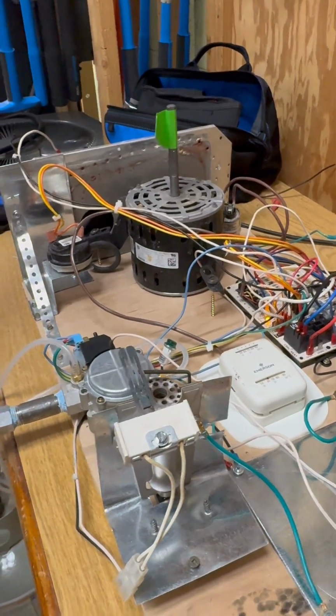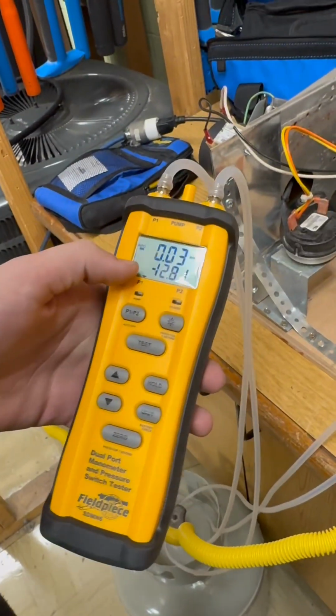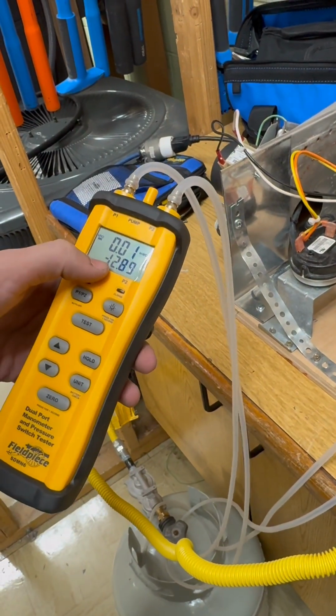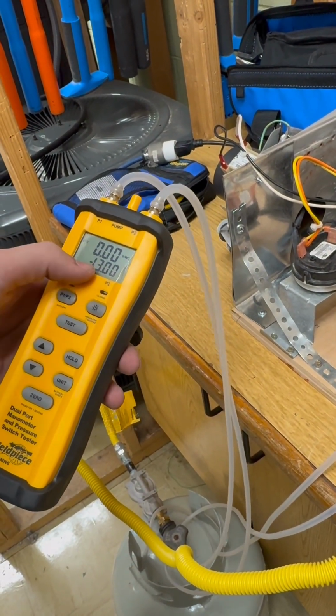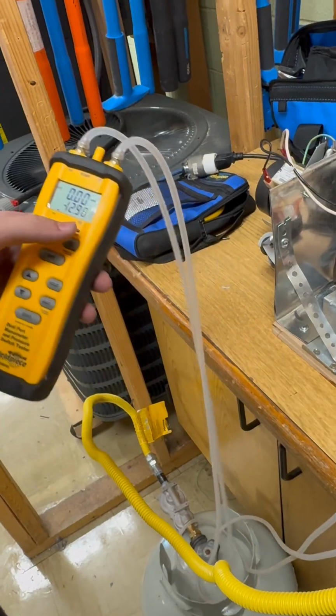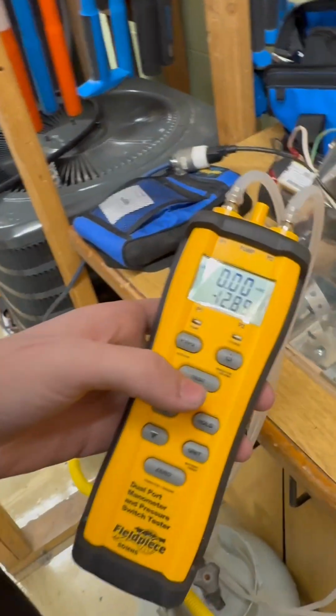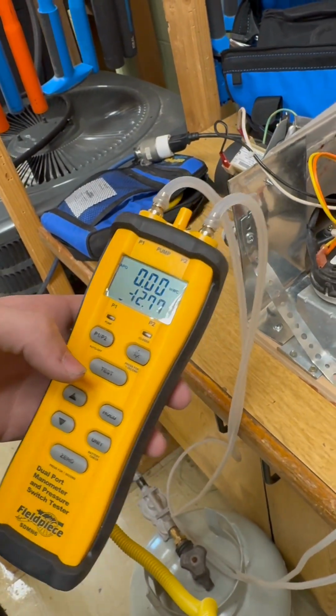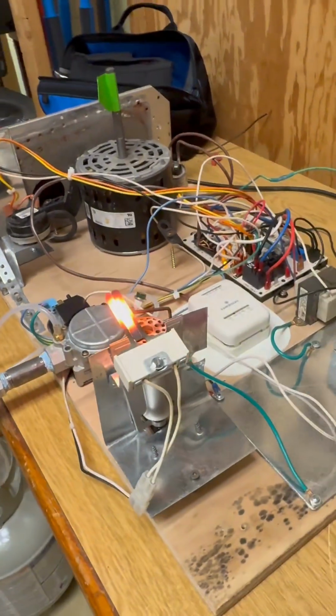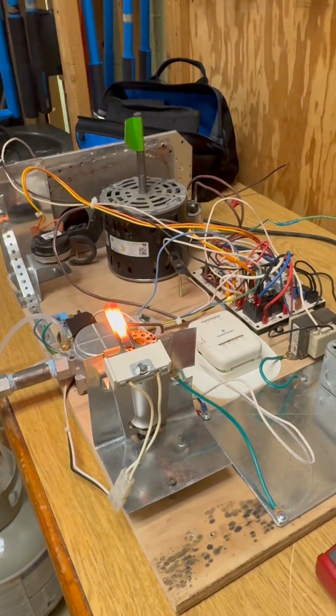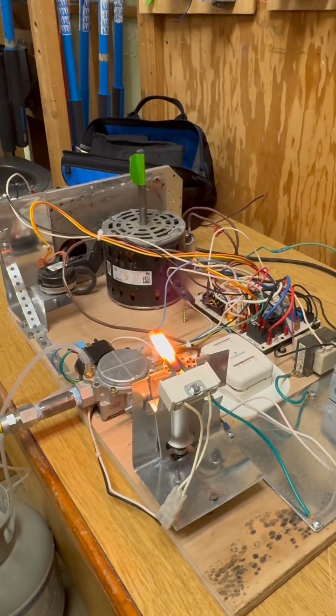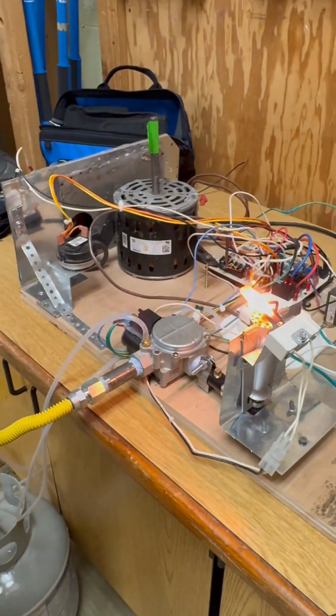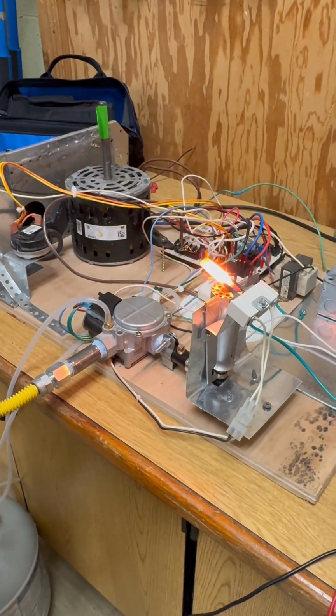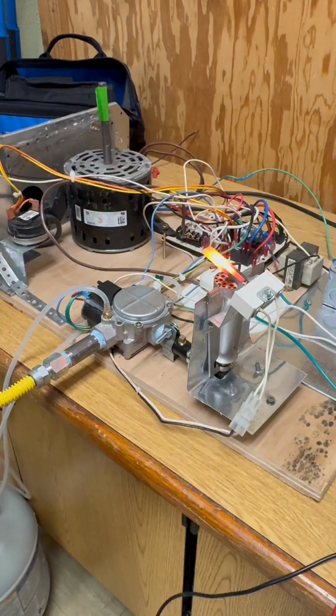And for that, we're going to use a manometer. So you can see our inlet pressure is 12.9 inches or 13 inches of water column. And then if the gas valve triggers, it will jump up on our opposite side. So we have our igniter, and we heard the click from our board that should open the gas valve, and our gas valve did not light.